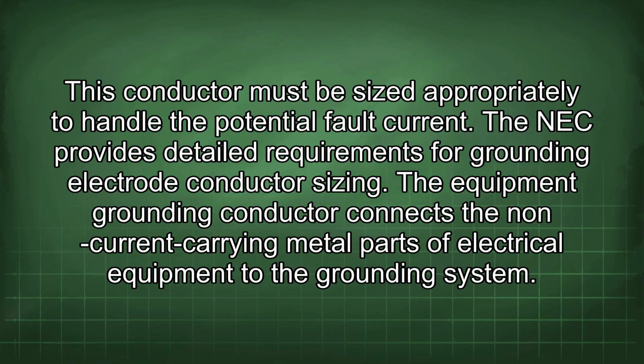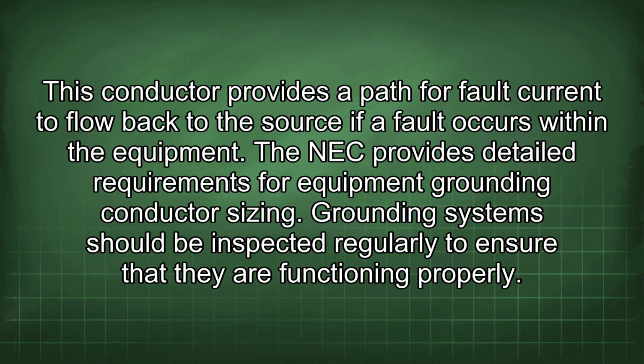The equipment grounding conductor connects the non-current carrying metal parts of electrical equipment to the grounding system. This conductor provides a path for fault current to flow back to the source if a fault occurs within the equipment. The NEC provides detailed requirements for equipment grounding conductor sizing.